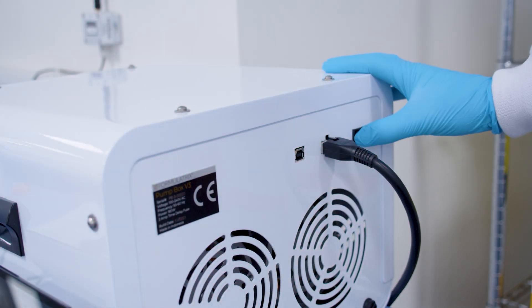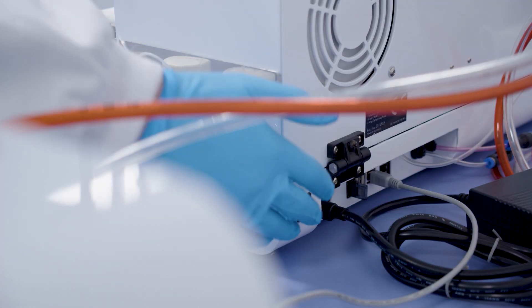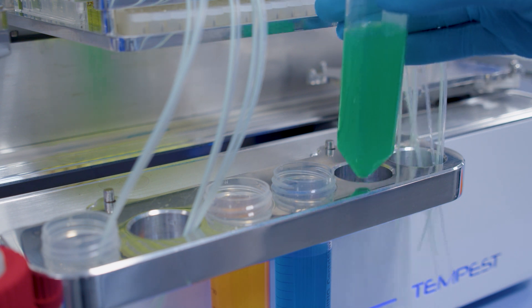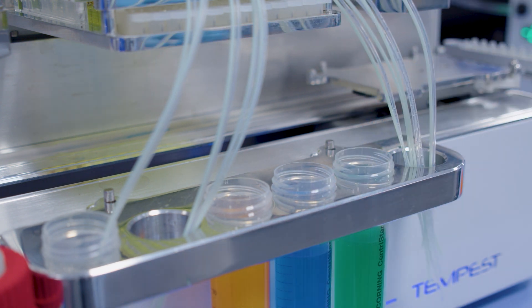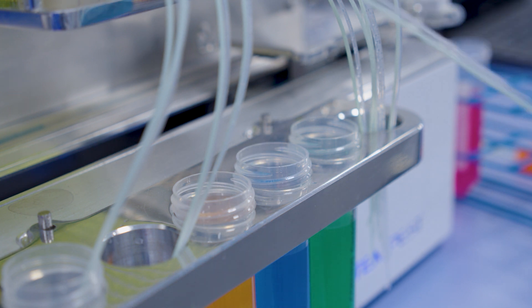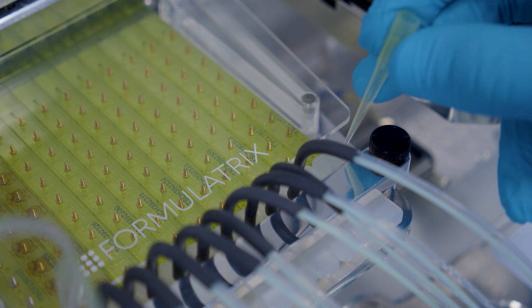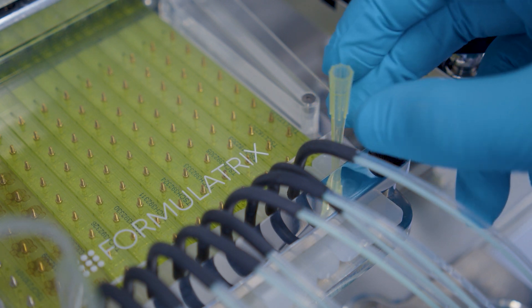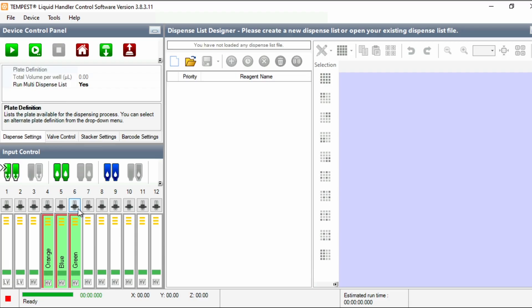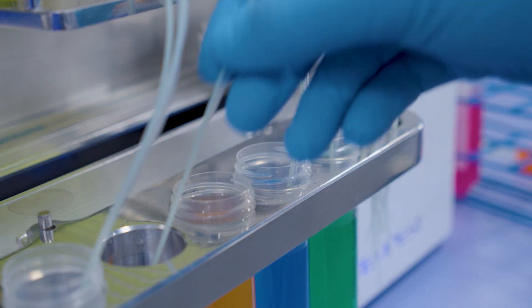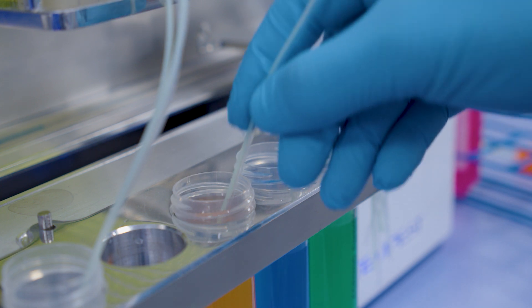First, you'll need to turn on the pump and the device itself. Then load the input liquids to the positions you selected previously. Simply place the tubing from the chip into your input liquid container. If you want to use a pipette tip as your input container, attach it to the chip and choose a tip as your container type on the Tempest software. The ordering of the liquids on the input positions doesn't matter as long as they're connected to the correct chip.